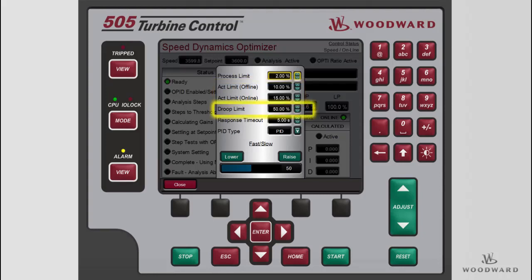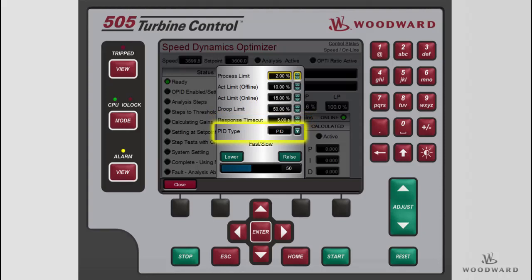The droop limit limits the amount of droop signal movement allowed when using generator-load droop. If movement occurs during automatic tuning that is more than this value, the automated test routine will be aborted and controlled at the initial setpoint. The response timeout in seconds determines how long the automated test routine will wait for a response after moving the actuator. The value should be at least two times longer than the system's slew and settling time. During the setpoint step mode, this value determines the step times and times between steps. A fault and abort will occur if the total test time exceeds a value of 40 times the response timeout. The PID type determines the mode of the PID controller. The Fast-Slow setting allows for the calculated system response to be more or less aggressive. If faster response time is needed, this value should be increased; if slower response time is needed, this value should be decreased.